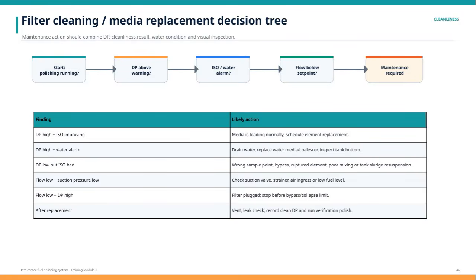Let's walk through the filter cleaning and media replacement decision tree. When deciding on maintenance actions, it's important to look at several factors together: differential pressure, cleanliness results, water conditions, and visual inspection. We start by asking if the polishing system is running. Next, check if the differential pressure is above the warning threshold. Then look for any ISO or water alarms. If the flow rate is below the set point, that's another red flag. Depending on these observations, different maintenance steps are recommended.